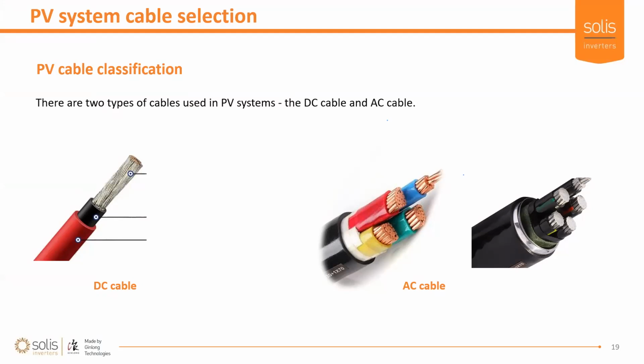Your AC cables, you often see the phases all bundled together, so multiple cores in a single cable. That's absolutely fine, as long as they've got isolation between each of the phases, so that's all good. Whereas the DC cables, you don't really want to run them all in a single cable, multiple cores in a single cable. It brings up phenomena like parasitic capacitances and annoying things like that you really don't want in your system. Extra headaches that you have to analyze and work out. So yeah, single cables for DC are generally a better idea.